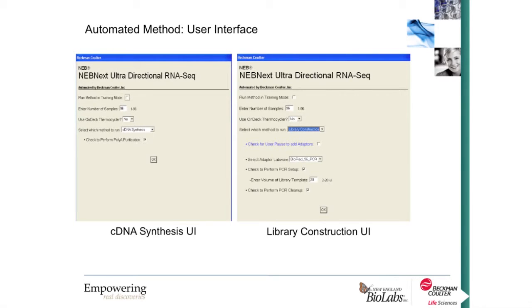Our automated method on the Biomek FXP includes an HTML-driven user interface that allows any user to run through the method without needing to know Biomek programming specifics. The cDNA synthesis user interface offers a training mode option — clicking this box will run the method in simulation, allowing you to train technicians more effectively. In live mode, you can enter the number of samples up to 96, and choose between on-deck or off-deck thermocycling. For on-deck thermocycling, we have an integration with the Biometra T-Robot. If you choose off-deck, the method creates several pause steps allowing you to take the plate off and use your thermocycler of choice.